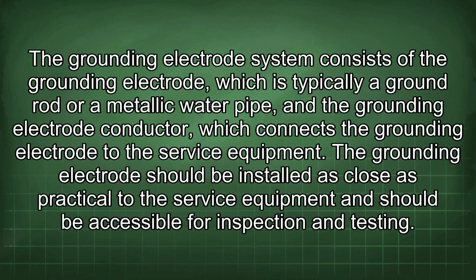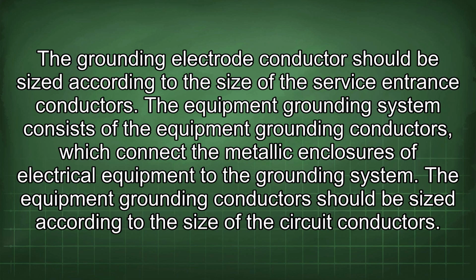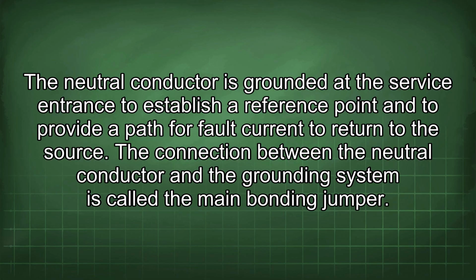The grounding electrode should be installed as close as practical to the service equipment and should be accessible for inspection and testing. The grounding electrode conductor should be sized according to the size of the service entrance conductors. The equipment grounding system consists of the equipment grounding conductors, which connect the metallic enclosures of electrical equipment to the grounding system. The equipment grounding conductors should be sized according to the size of the circuit conductors. The neutral conductor is grounded at the service entrance to establish a reference point and to provide a path for fault current to return to the source.